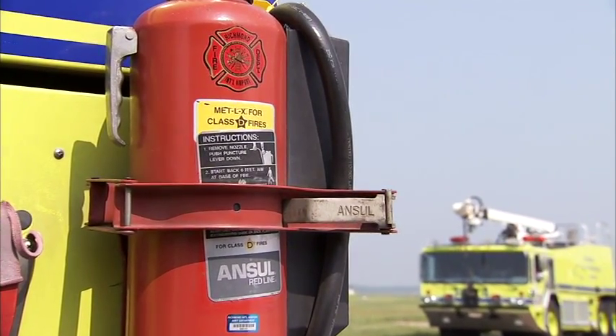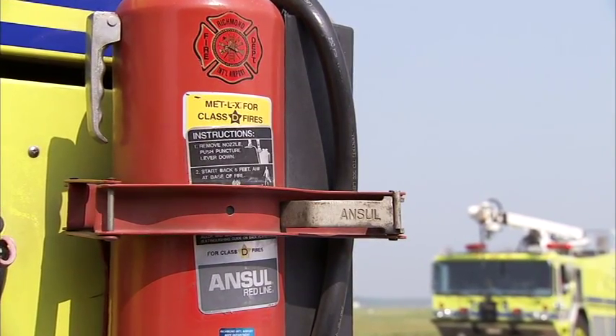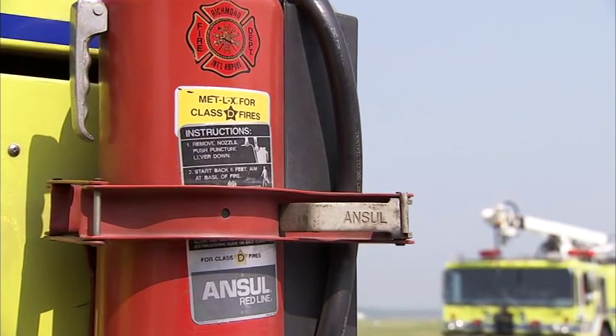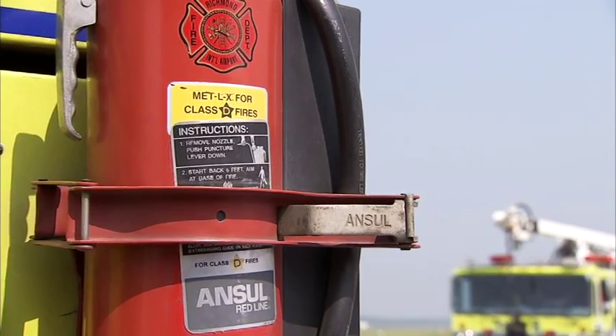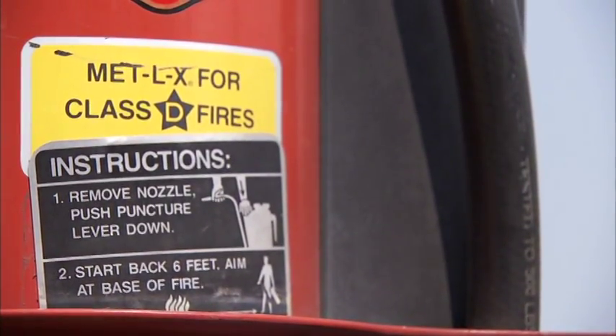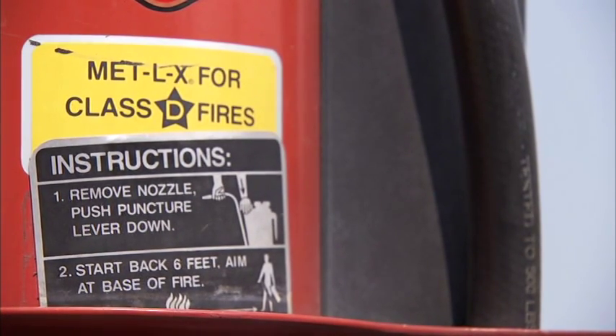Dry powders are used exclusively on combustible metals. Dry powders have a yellow star on the extinguisher label. Met-LX powder is the most common dry powder. It is non-toxic, non-abrasive, and non-conductive. Heat from the fire causes the powder to form an air-excluding crust, and it clings well to vertical surfaces. Most dry powders are useful on small fires because they withdraw oxygen and lower the temperature of the burning metal below its ignition temperature.